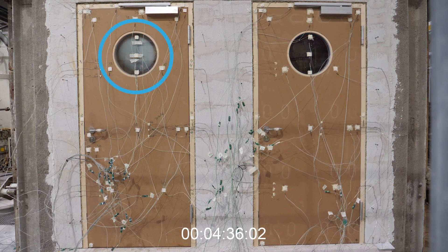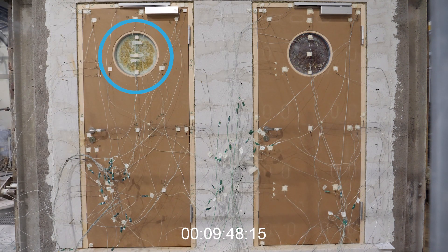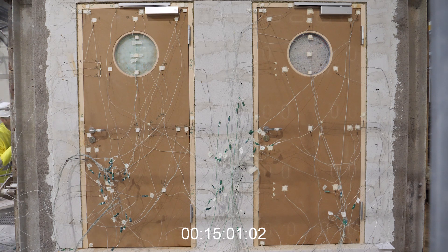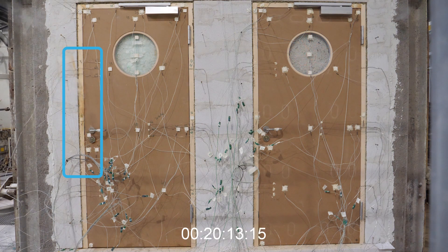On the left door please have a look at the critical areas, which are the gap between the door leaf and the door frame on the top, the glass and the door locker. After four minutes you can already see that the 60-minute fire rated glass reacts more quickly because the glass is thinner. On the incorrectly installed door on the left you already see gaps between the block frame and the door leaf, because there is no intumescent in the door frame and we have a less performing intumescent in the door, meaning the joints are not closing properly.